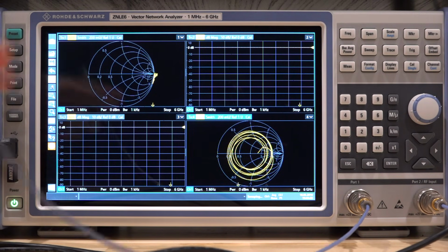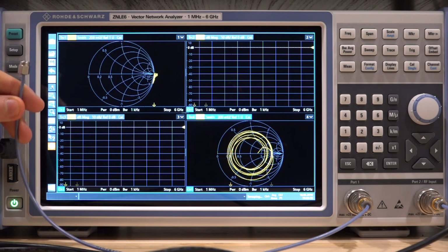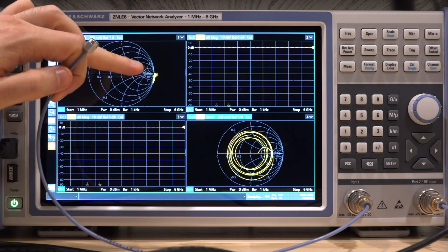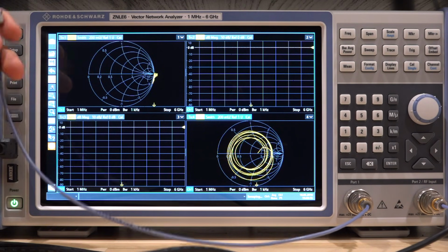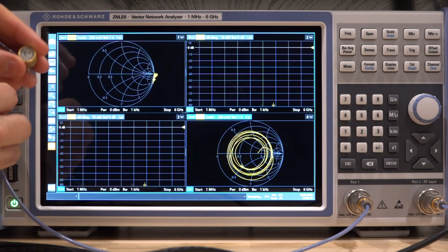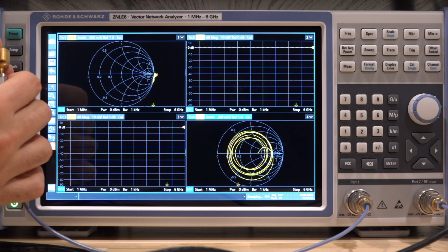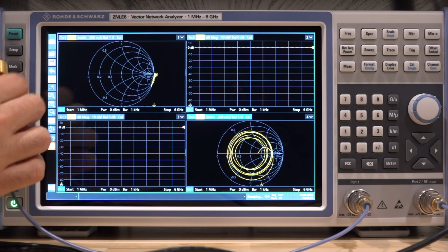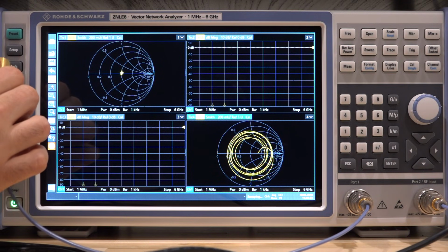So here I have disconnected port 1. You can see it's disconnected, and you can see the S parameter S11 directly on the outside of the Smith chart there. So I'm going to terminate it into a termination from my calibration kit just to show you that indeed we do have a calibration that we can observe on the Smith chart.